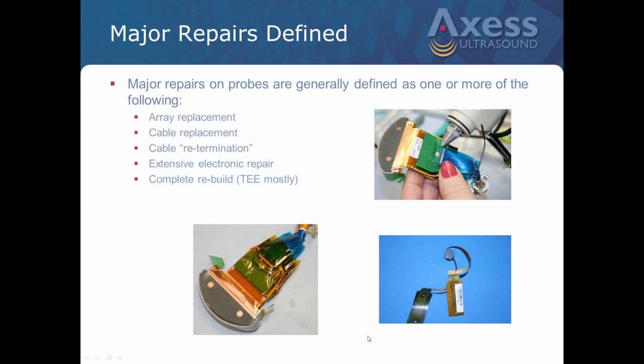We work with our friends at Acertara here, who are an FDA acoustic lab themselves, and we do the acoustic power testing here, and then they perform the reading. So we make sure that any replacement arrays we use do not exceed those limits. That's where the FDA will frown on that, and there could be some problems. You've got to make sure that the replacement array is performing as close to the original equipment manufacturer's array as possible. For us, a good example was the Philips C5-1 array.